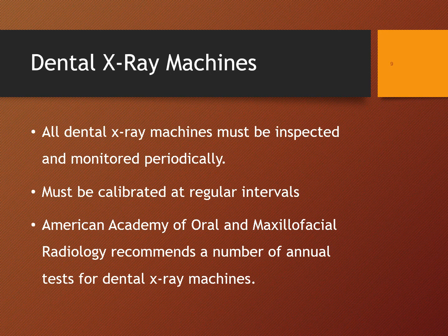And then the American Academy of Oral and Maxillofacial Radiology recommends a number of annual tests for dental x-ray machines. Typically, a representative will come, some type of service person will come and check the machine and give the dentist some type of reading. There are local and state regulatory agencies that provide some of those inspection services. It's always at a cost. And then the dentist, the dental hygienist, dental assistants, or the manufacturer service representative can perform those annual tests. It's not just that service representative.